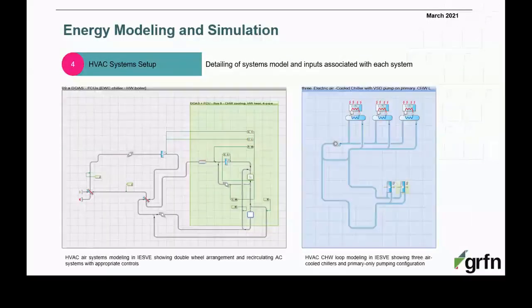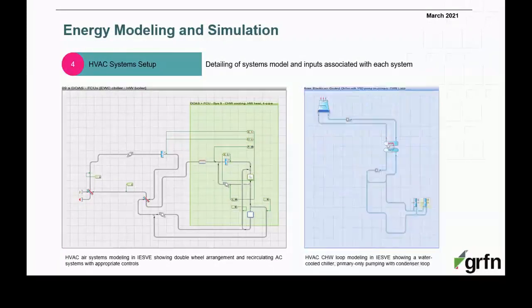Here we can see the HVAC system setup. In both cases, the original design and the net zero energy case, we've used outside air handling units, double heat recovery, and fan coils to cool down the spaces. In the original case, we had air-cooled chillers with a variable primary system. Here we can see the configuration for the net zero energy case. For the air side, it's the same as the base case. The main difference would be the efficiencies of the heat recovery devices.